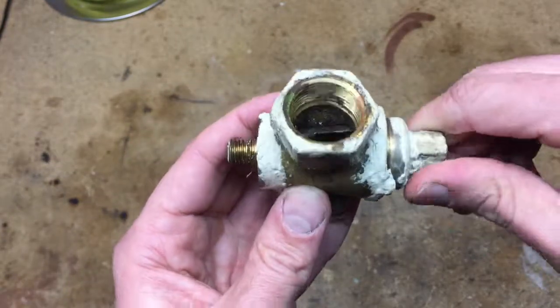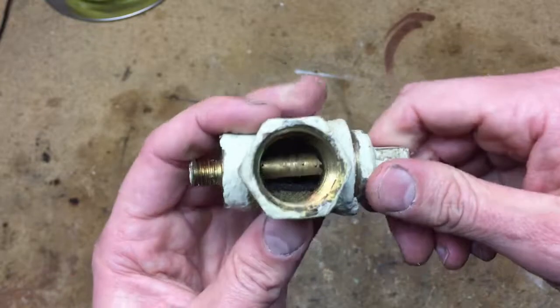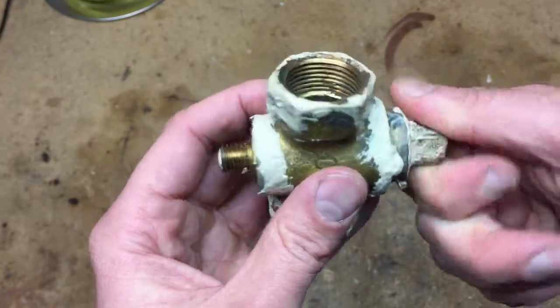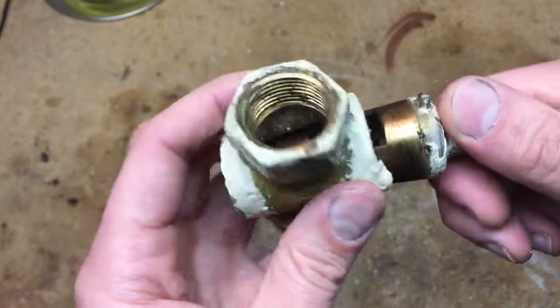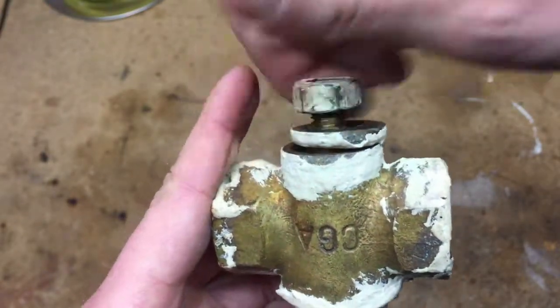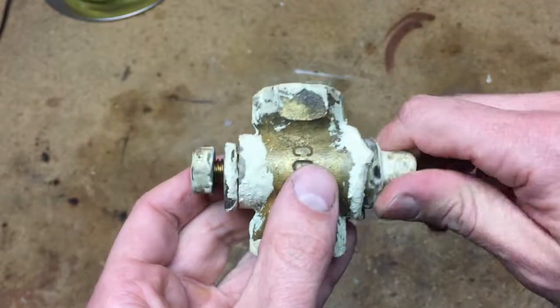This one we pulled off the gas water heater because it was leaking. You can see the previous owner put a bunch of piping dope compound on it, not realizing that's not going to seal it — it's the grease. Look at the grease; it's worn out and all dried. I could smell just a fair bit of natural gas, that rotten egg smell. I put my nose right to the valve and it was leaking from this. You can typically tighten the end here and it pulls the taper further in, but then it becomes hard to turn, and if you need to turn it off in an emergency that's not much use.